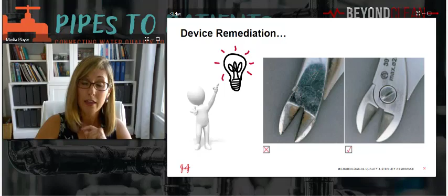That can work, but I caution you to be very careful about that and make sure that the original medical device manufacturer has approved this type of remediation. Resurfacing or taking off things like rusting, pitting, or cracks and crevices might look beautiful to the naked eye, but when you look at it on a microscopic scale, you've actually removed what has already deposited, and you've left big holes in the material surface itself that can cause a problem in the continued cleaning and sterilization of those devices over time. If you make more microscopic areas for soil and microorganisms to get lodged, it becomes more and more of a challenge and an increased patient safety risk.